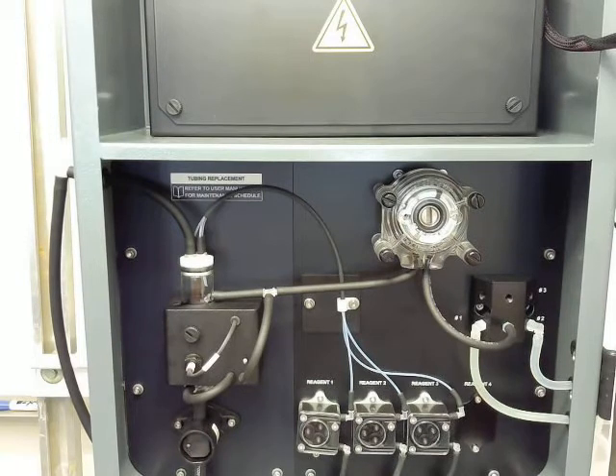After the first drain, it'll fill up again a second time, drain out, and then the third time it fills up will be the sample volume that we use for a reaction. Once that third flow cell fill happens, we're done with the sample pump until the end rinse out, and that volume is the sample we're going to use for our analysis. So say we were to lose flow online after this point, the analyzer will continue to finish this cycle. It knows, hey, I had enough sample to start, my flow cell's filled, we can finish the sample, and then at the end of the next one, we'll go to standby once we get sample back.